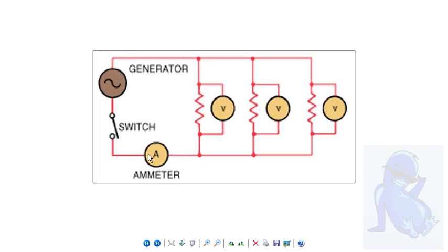Amps are done while everything's working, while electrons are flowing. Voltage, you're going to measure voltage across the load or across an open switch. So it's going to be a measurement of the electrical pressure. Resistance is measured with the ohm setting on your multimeter, and your power has to be off or you're going to ruin your meter. So you take a measurement of the resistance across the load on both sides.